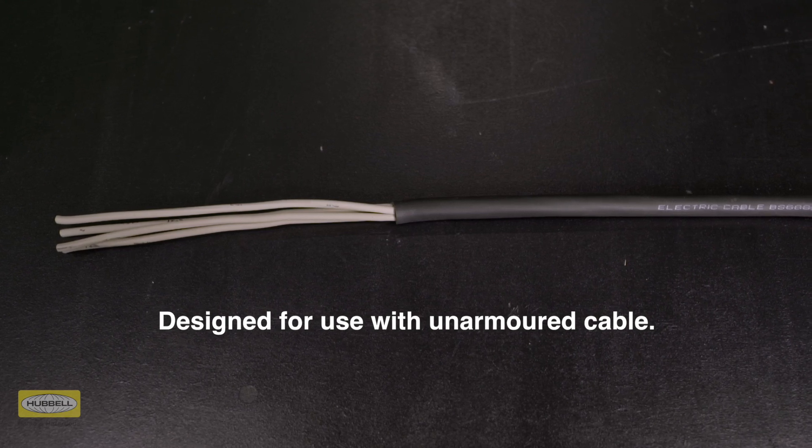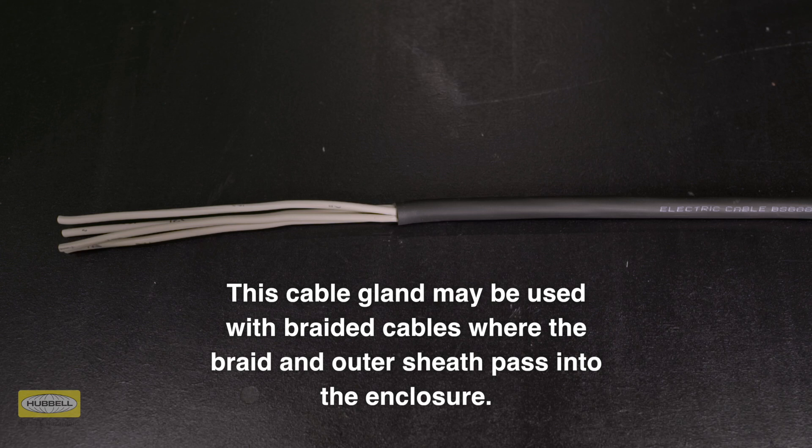This Ex e cable gland is designed for use with non-armoured elastomer and plastic insulated cables. This cable gland may be used with braided cables where the braid and outer sheath pass into the enclosure. The braid must be suitably terminated inside the enclosure.